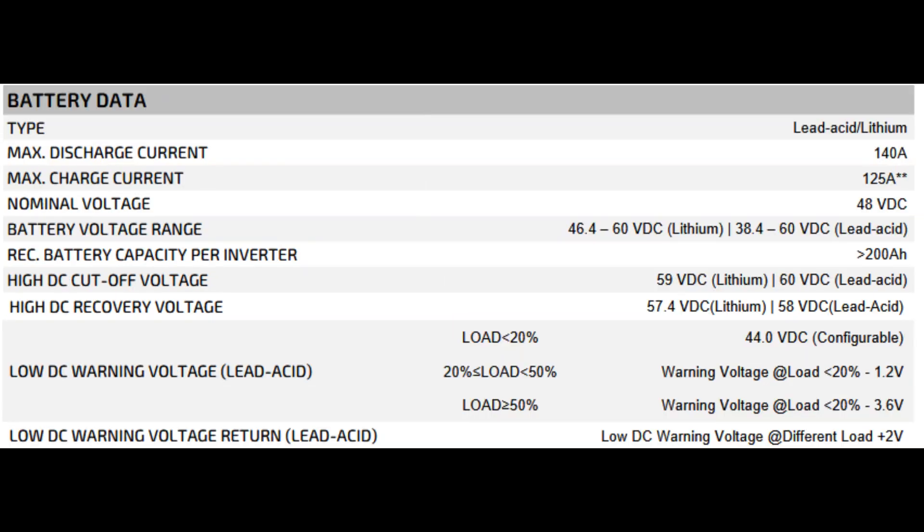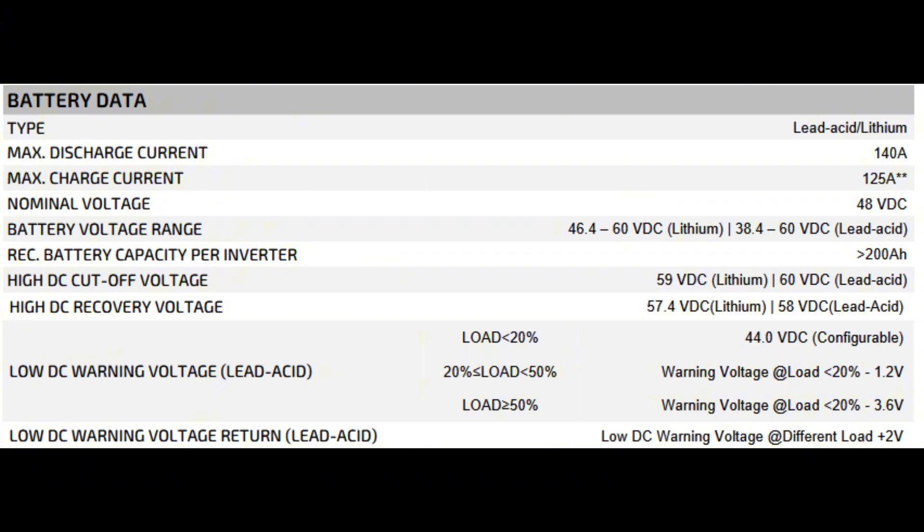Now the all-important battery data. Type, lead acid slash lithium. Max discharge current 140 amps. Max charge current 125 amps. Nominal voltage 48 volts DC. Battery voltage range 46.4 to 60 volts DC lithium, or 38.4 to 60 volts DC lead acid. Recommended battery capacity per inverter greater than 200 amp hours. High DC cutoff voltage 59 volts DC lithium and 60 volts DC lead acid.